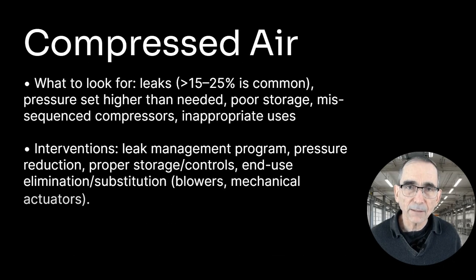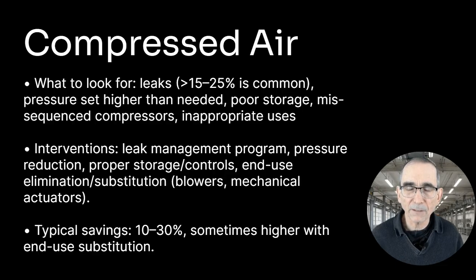With compressed air, leaks are a common problem that often needs continuous attention. Therefore, it's not just a once-off item to fix. It needs more of an internal change in how you manage the leaks and how you continue to monitor them. And possibly that could be wasting 15 to 25%. The pressures may be set higher than needed. There could be poor storage, poor air distribution, mis-sequenced compressors, and inappropriate use of air, such as using compressed air to blow something down. So the interventions are leak management programs, pressure reduction, properly sized storage, and controls and distribution of air.